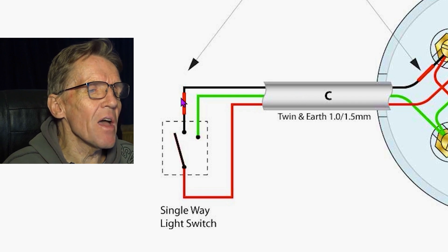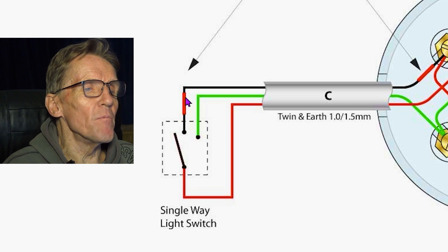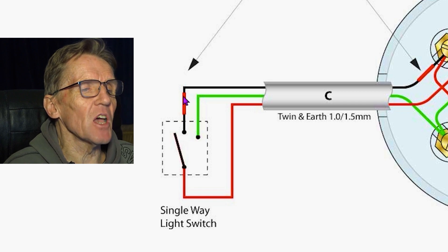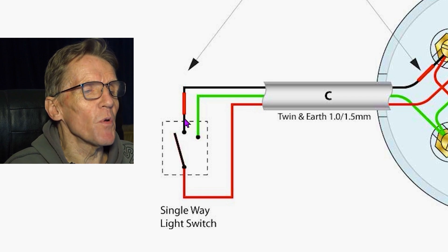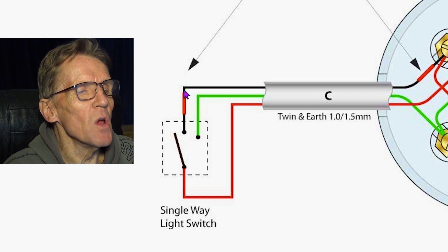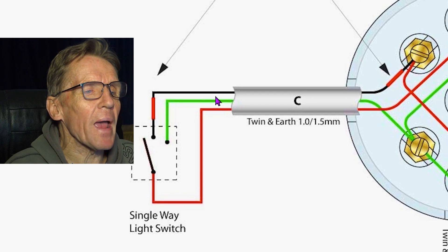But we've now said that this is a live wire, it's not a neutral wire, so hence he's put a red flag on it there—a bit of tape around it. And now you would get a brown sleeve and you would put the brown sleeve over the black, so that you've nominated this as live.